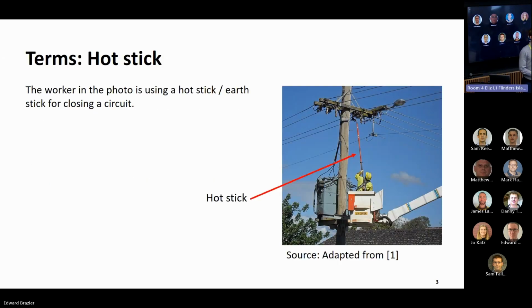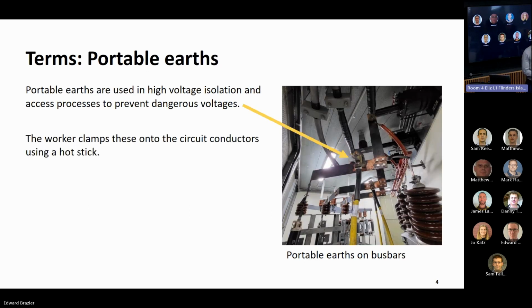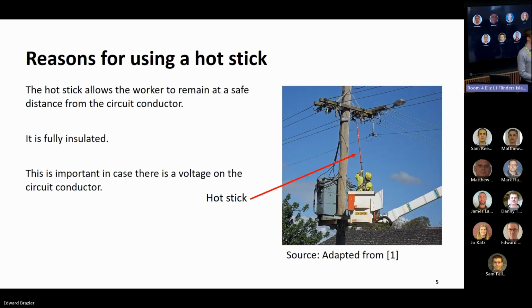Some key terms: this is a hot stick in red in this photo, and these are portable earths, the yellow cables with the metal clamps connected. Portable earths are used in high voltage isolation to prevent dangerous voltages. When a worker goes to connect the portable earths, they use a hot stick for that purpose. The hot stick is important because it allows the worker to remain at a safe distance, and it's fully insulated, which matters because there could still be a voltage on the circuit conductor.